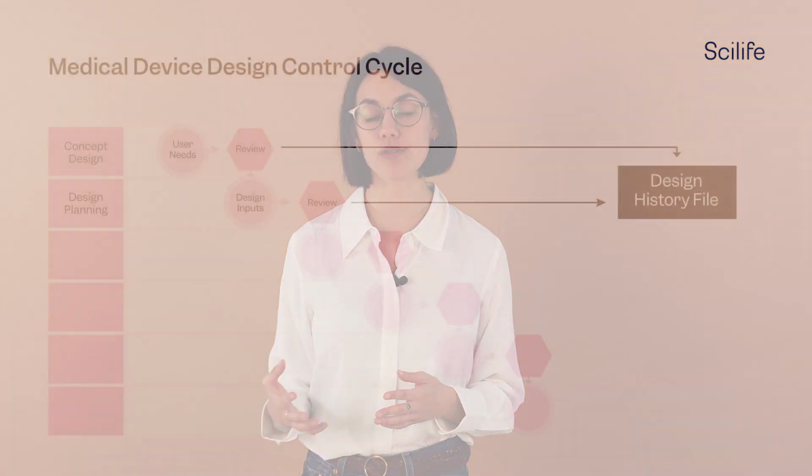The next step is design planning. At this stage, the manufacturer creates a design and development plan that outlines the complete process. The plan is not only for the design itself, but for the process too. Hence, details like who is responsible for which part of the design and manufacture, which team is responsible for what, etc., need to be included. In addition to that, responsibilities regarding overseeing and providing feedback during the process should also be outlined clearly. The plans act as the blueprint, so if the design changes, the plan will also change.